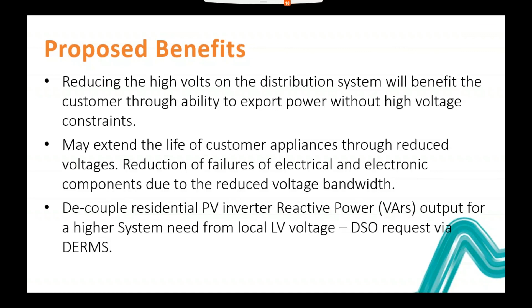The other proposed benefit is that we would decouple the residential PV inverter reactive power output from the street, so we could ask all the DERs to provide us with what we wanted in a controlled way, decoupled from the source voltage, which we could control separately. So that was an extra nice to have.